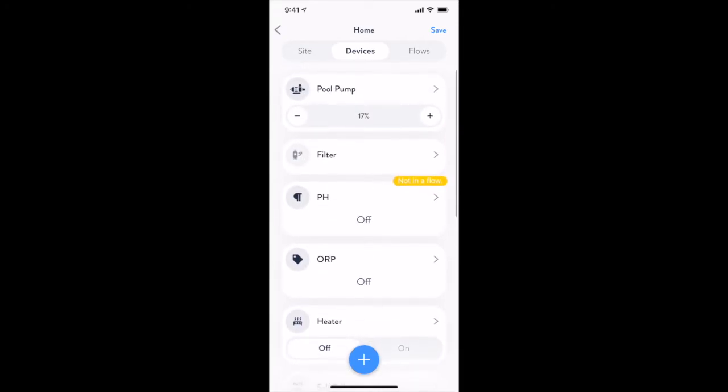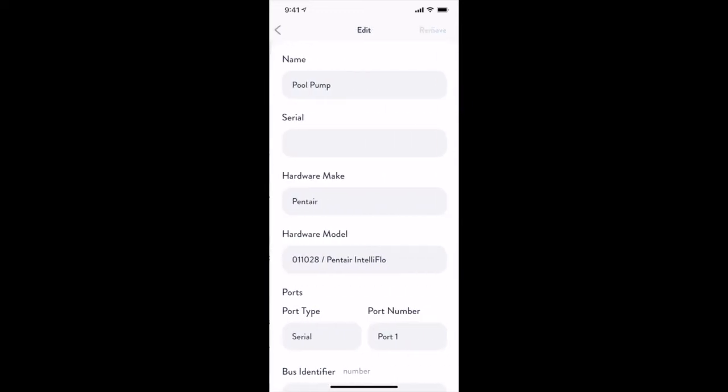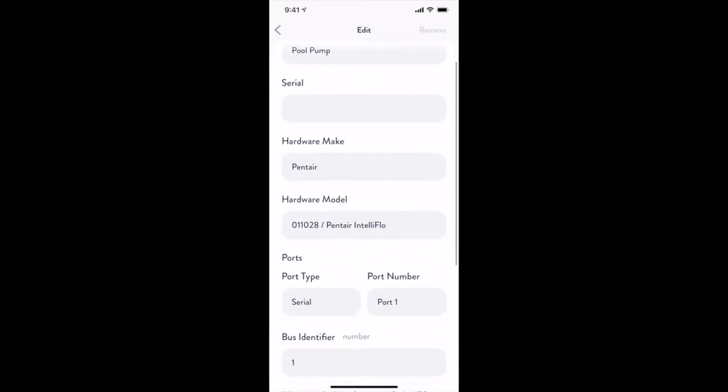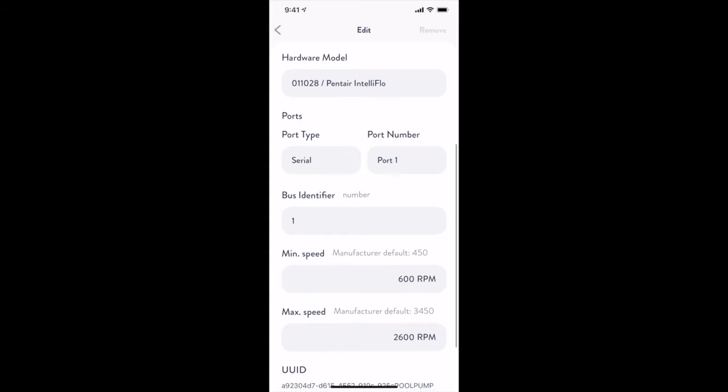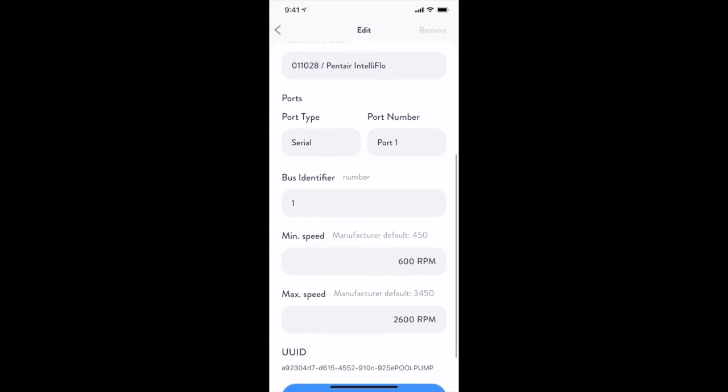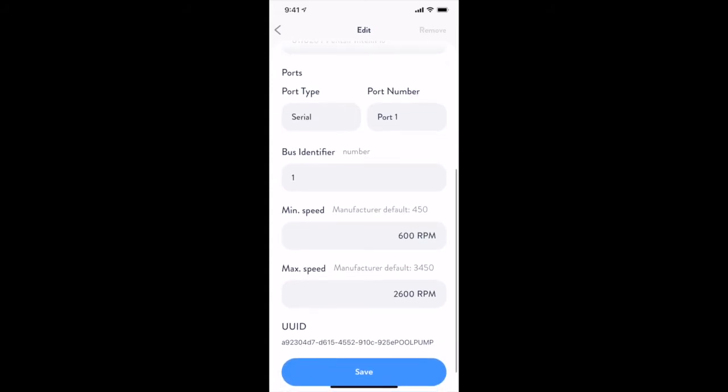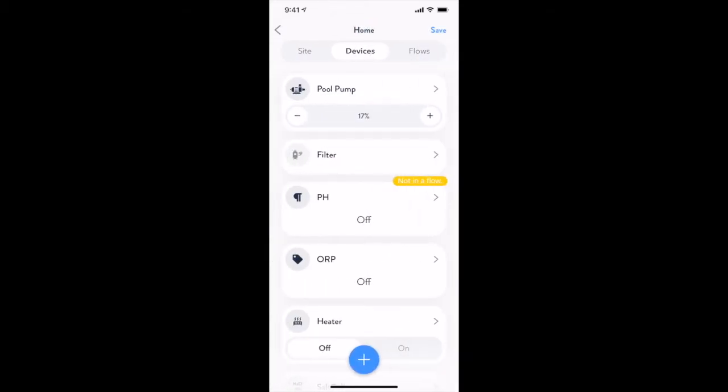From this tab, you can also turn individual devices on or off in order to troubleshoot their installation and settings. For example, here I am configuring the minimum and maximum RPM that I want my pump to operate at. Saving this, I can now test this device by powering it on and setting the speed up to 100%.